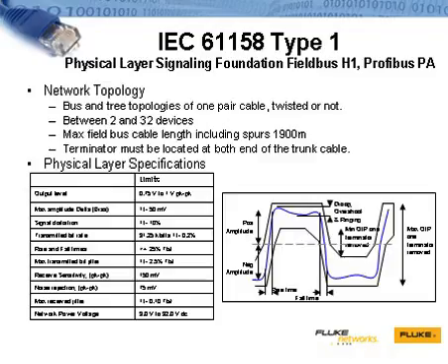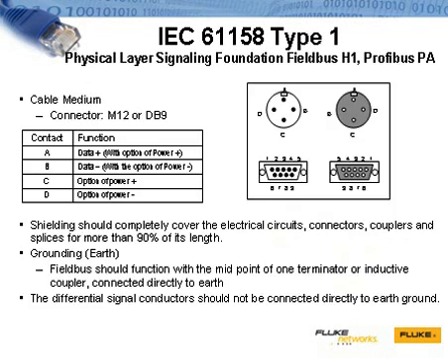Next, to ensure the encoded signals are transmitted from point A to B correctly, the standard will typically define key electrical characteristics the encoded signal must conform to. Often the specifications are divided into the signal's amplitude and time domain, plus signal quality characteristics like noise rejection, distortion, and jitter. Lastly, the standard will define the cable medium and the connectors. A more recent innovation is the M12 connector, designed to offer better resistance to environmental ailments like dust and moisture found in today's industrial plants.